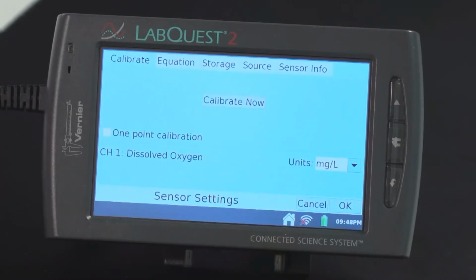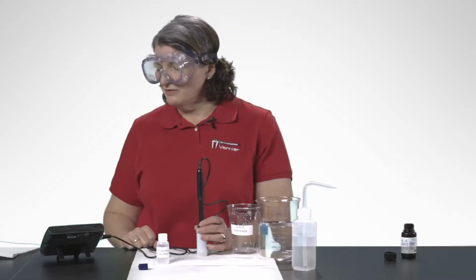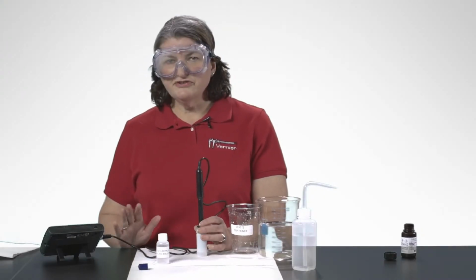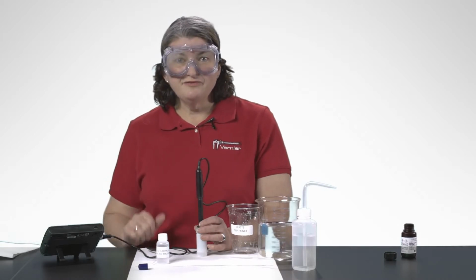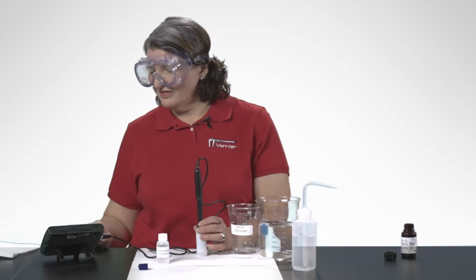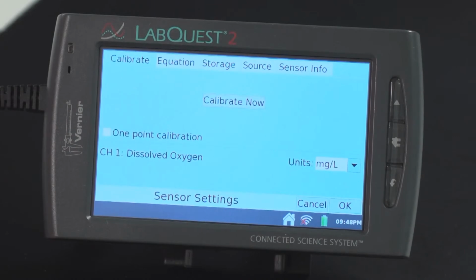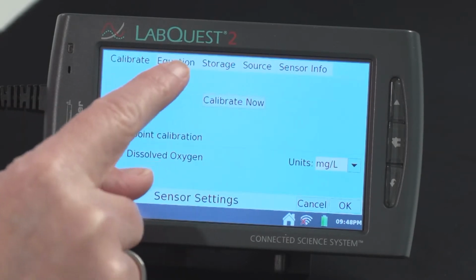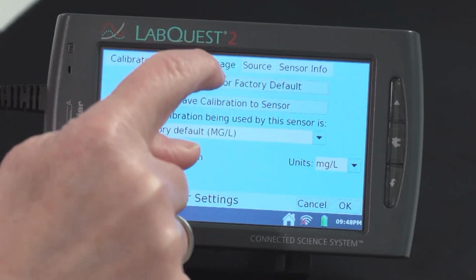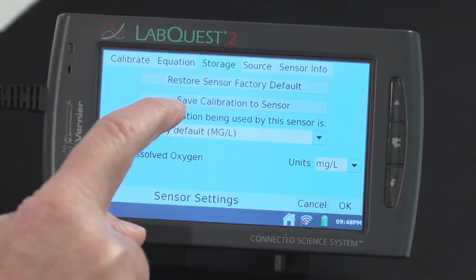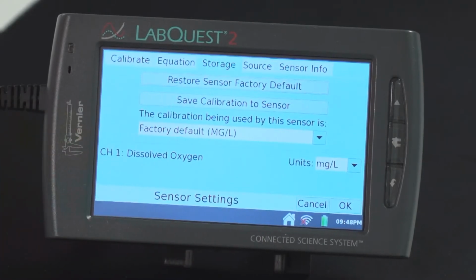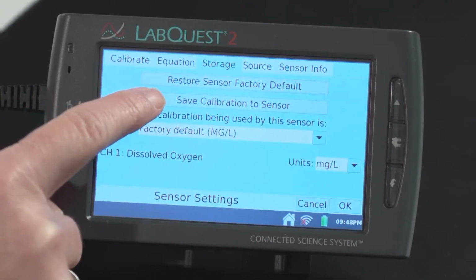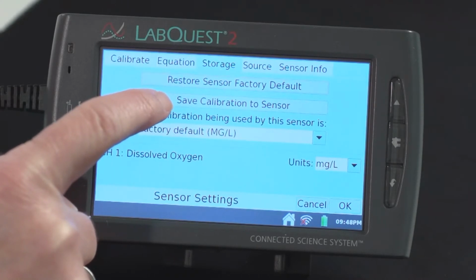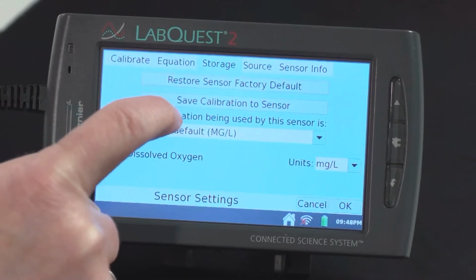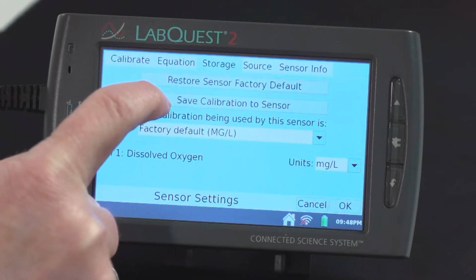All right, so we're back to the calibrate screen. Now we're going to do one more thing while we're here. And this is a feature of many probes that a lot of people don't know, so it's good to learn this. We have 5 tabs across the top of this screen. One of them is called storage. You tap on that tab and you get a button here that says save the calibration to the sensor. This will save what we just did so that the sensor is going to remember it. Whether we unplug it, move it to a different LabQuest, it will put it right on the sensor's electronics.